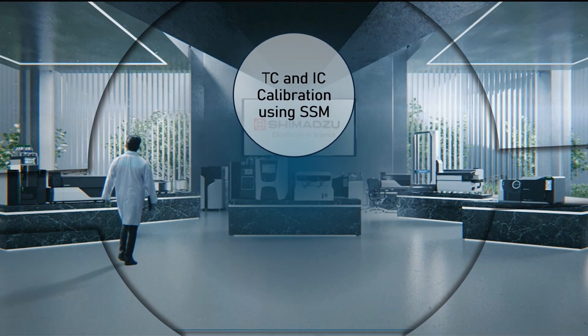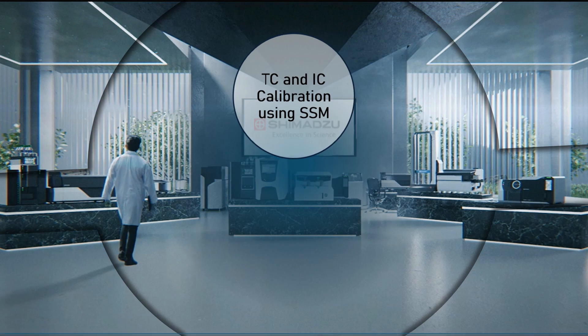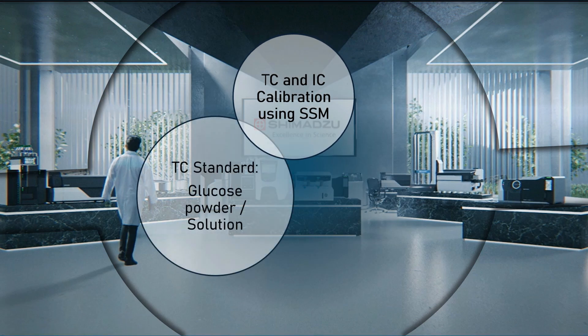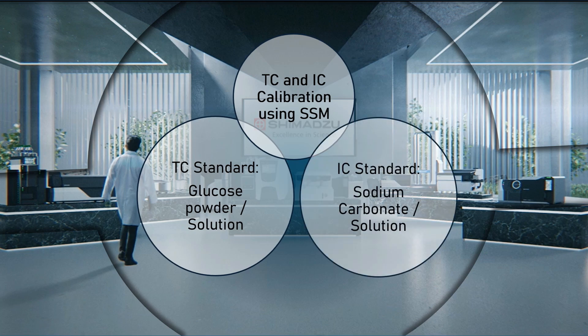Now let's talk about TC and IC calibration using the SSM. For TC calibration, you can use glucose powder or solution. For IC calibration, use sodium carbonate or solution.